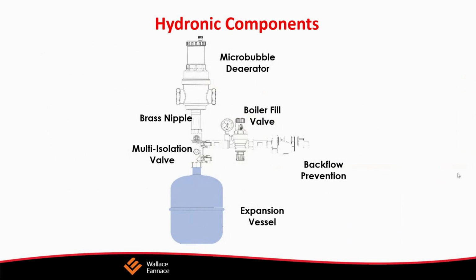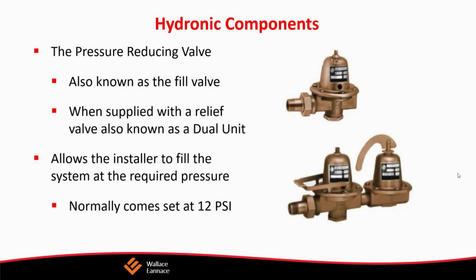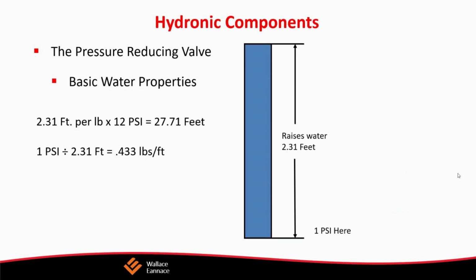The position of the tank is the point of no pressure change. Part of the purpose of that tank is not only to take up the volume of the expansion of water, it also maintains that point. The pressure never really changes. So the system should always be after that tank. So you're pumping away from the point of no pressure change. Here you can see the pump is now placed away from the expansion tank.